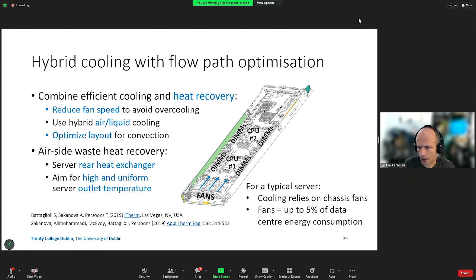And again, like we mentioned, for a typical server, there are no fans inside here. There are just fans upstream of the CPU, heatsink, and the DIMMs. And so these chassis fans basically have that dual function of both pushing the air through the system and carrying the heat, with the air that passes through the system, but also taking care of the local cooling. So what we want to do is to break up that coupling slightly, and deal with the DIMMs separately with air cooling.